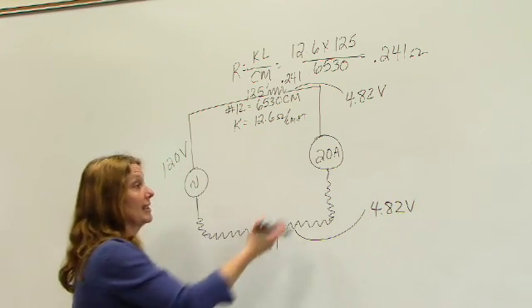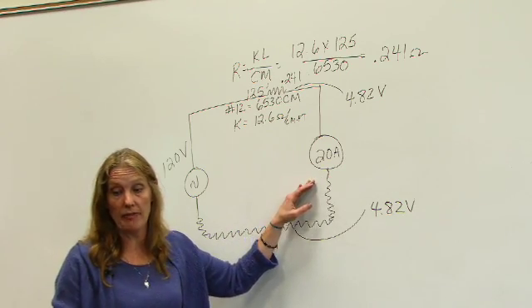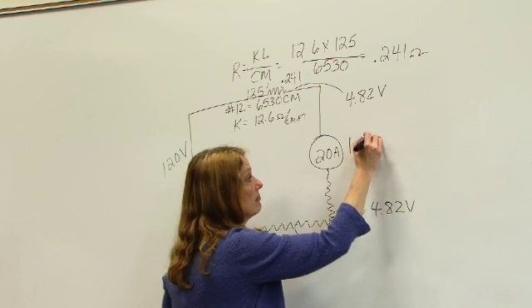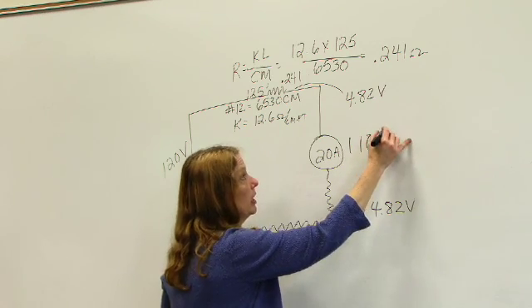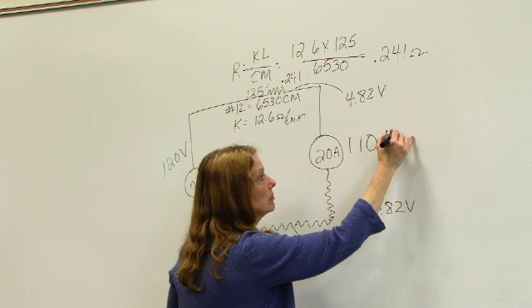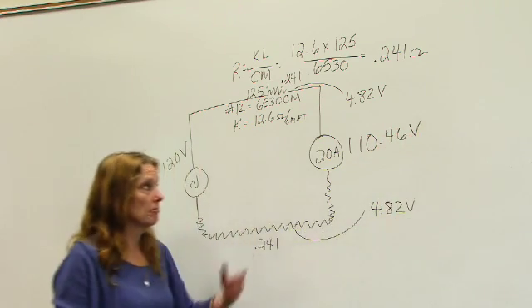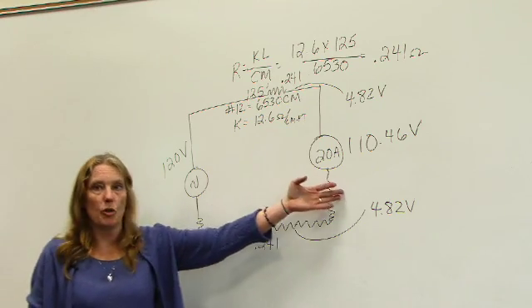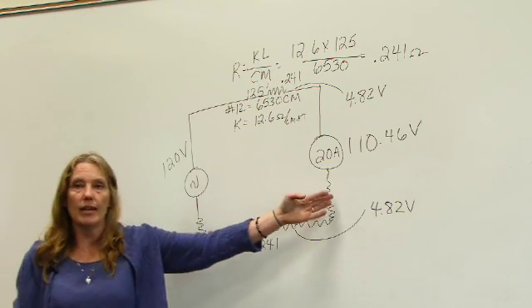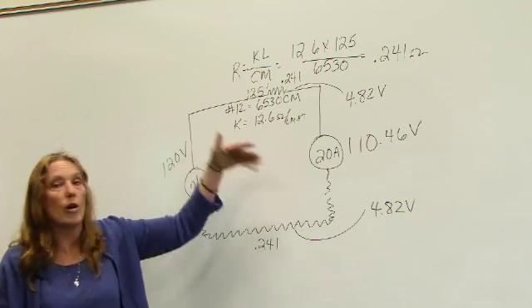What's left is what's going to be dropped here. What's left is 110.4 volts there. How much voltage there? I lost a whole lot of voltage there. That's the risk of wire. That's the risk of sizing our wire. Looking at what size we have, looking at the type of material we have, and looking at basically this end run. What we get.